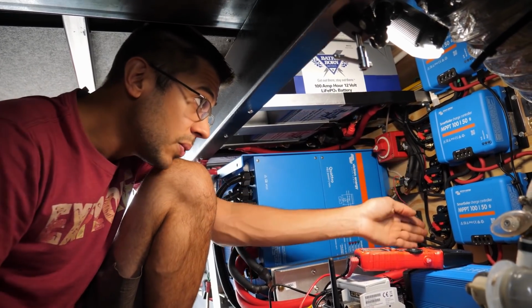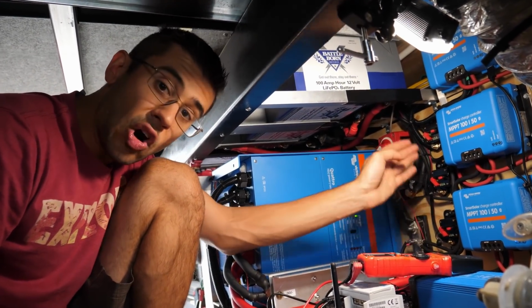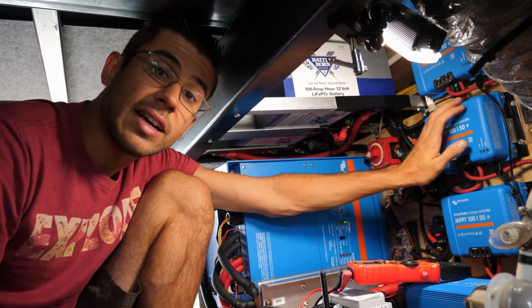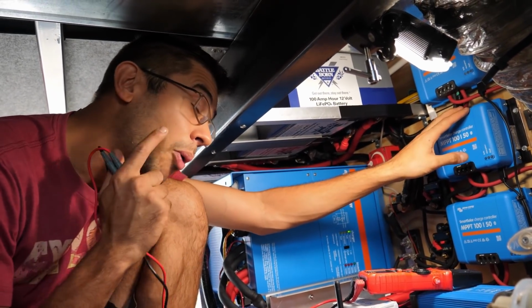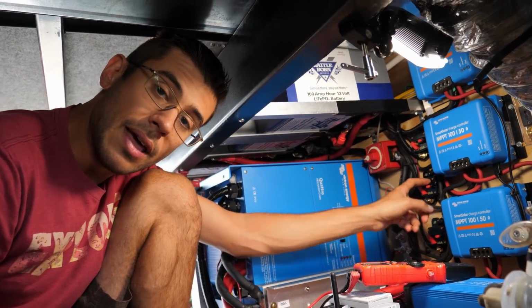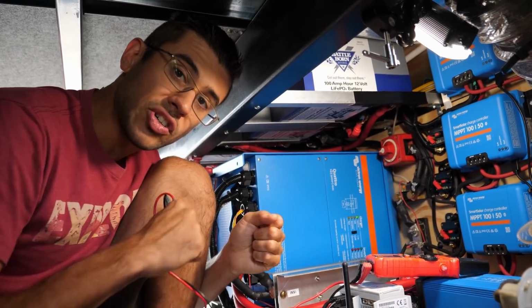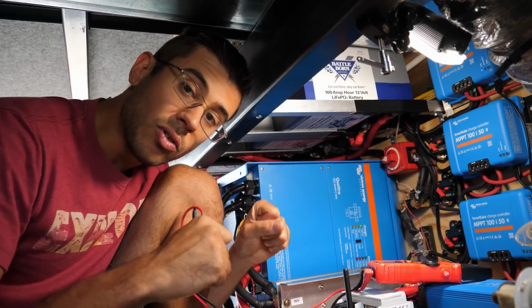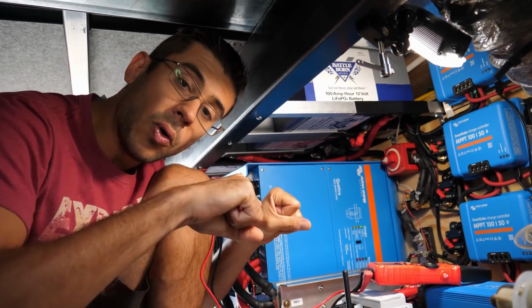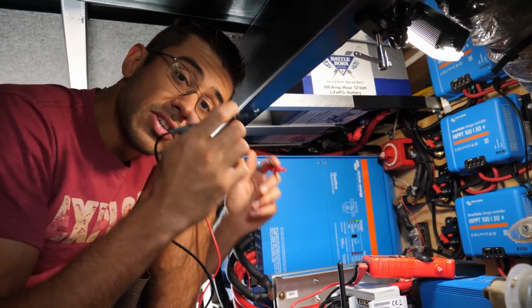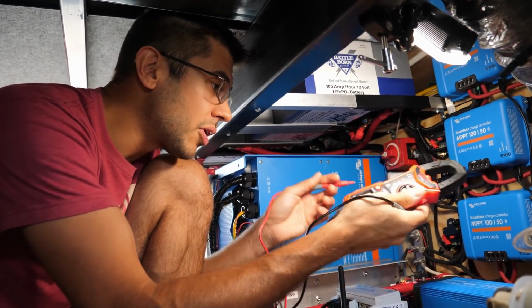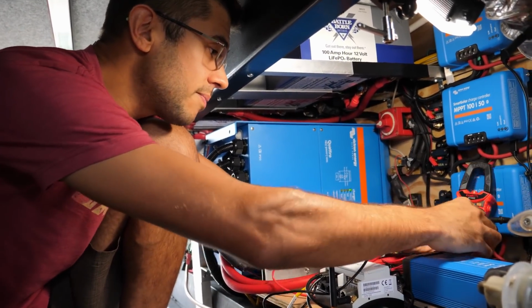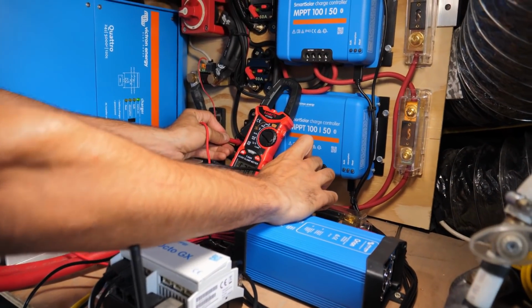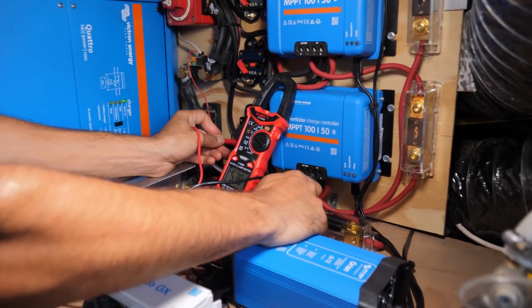We connected everything with the disconnects open down here, so it didn't fire anything up when the panels were first connected. It's important to have a disconnect in the system because you never want to make a connection to the solar panels under load, either in the bus bars or on the MC connectors on the roof. So there's no load in the system, but we're going to put our voltage meter in here, and 53.8 - we're seeing the right numbers, so that means our voltage is coming down properly.